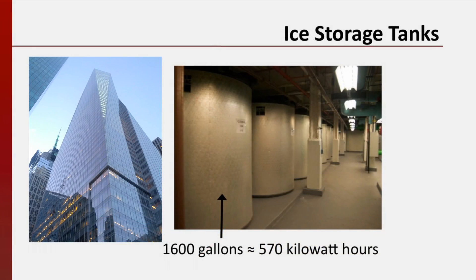One way we can decrease the amount of electricity needed in the daytime to cool a building is to use the energy storage capacity of ice, or its latent heat of melting. Large tanks, such as these in the basement of the Bank of America Tower in New York, store water that is frozen overnight using cheap electricity. During the day, the ice melts and absorbs energy from the cooling fluid running through the building's air conditioning system. Each of the tanks holds approximately 1,600 gallons of water, which translates to roughly 570 kilowatt hours of cooling capacity. Bank of America reports that these ice tanks supply 25% of their cooling energy annually.